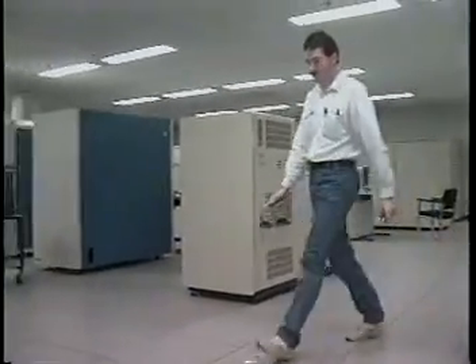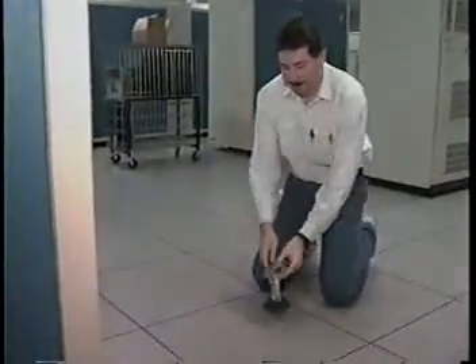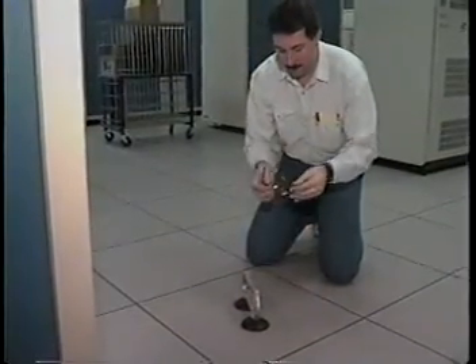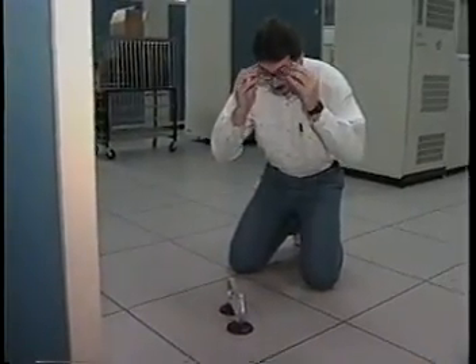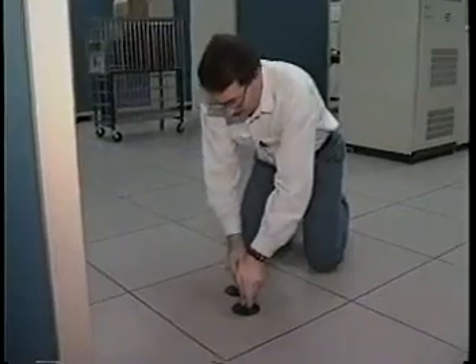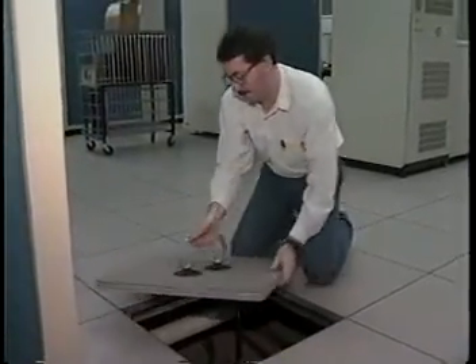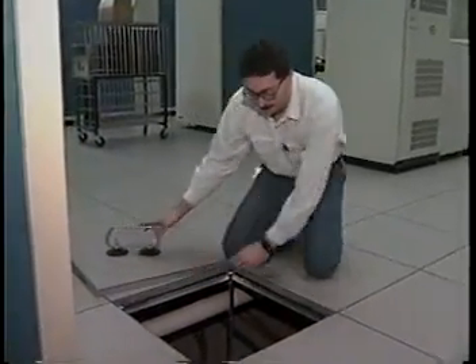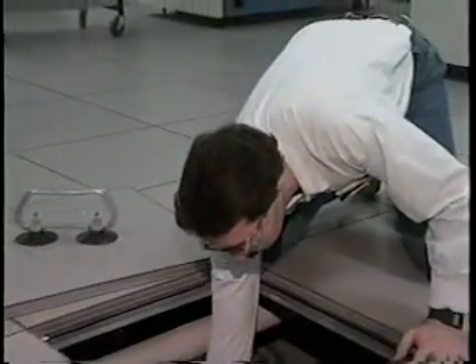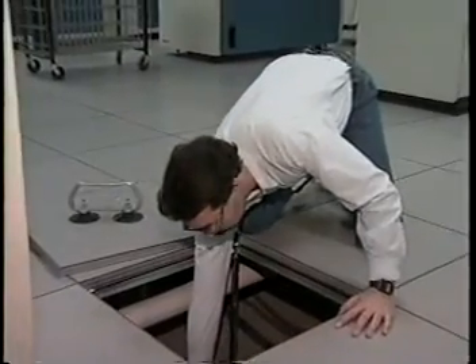Computer rooms with raised floors covering cable runs can pose hazards to unsuspecting technicians. Because the rooms are usually pressurized with the underfloor areas acting as air ducts, a sudden gush of air can result when a tile is removed for cable access. Fiber chips may be blown into the eyes of those not wearing safety glasses. For this reason, it is imperative that safety glasses be worn and that fiber debris not be dropped into open floor tiles.